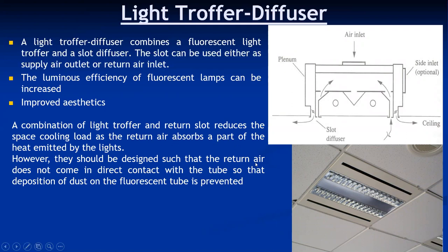The combination of a light troffer and return slot reduces the space cooling load, as the return air absorbs part of the heat emitted by the light. The luminous efficiency of the fluorescent lamp can be increased because cooling takes place via the return air, and it improves aesthetics since no separate diffusers are required. However, the system should be designed so that return air does not come in direct contact with the tube, to prevent dust deposition on the fluorescent tube.